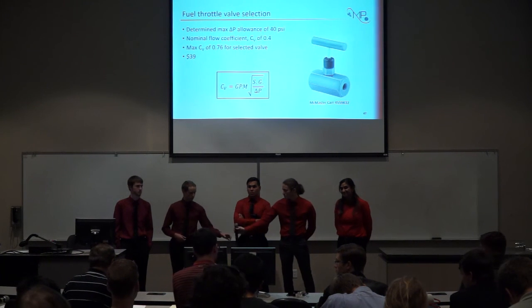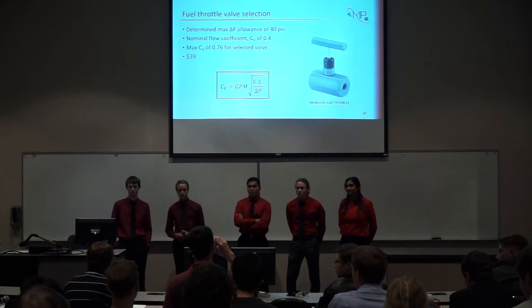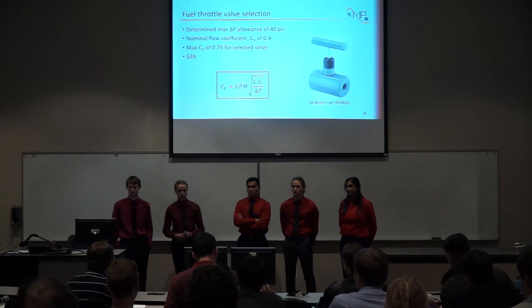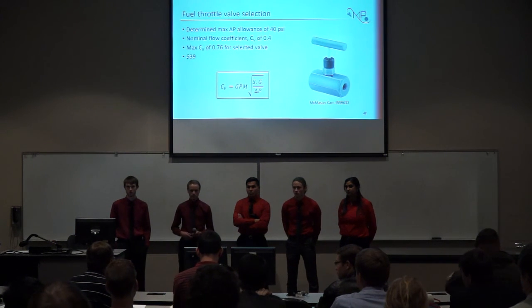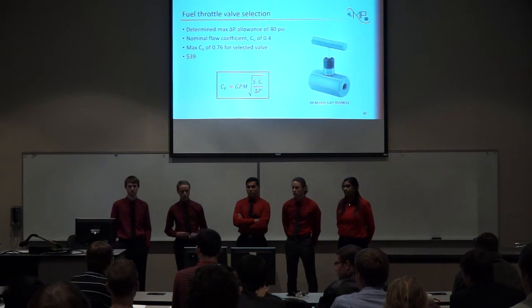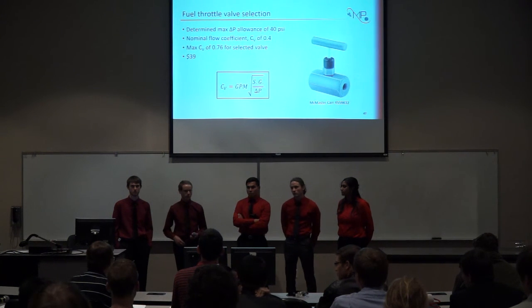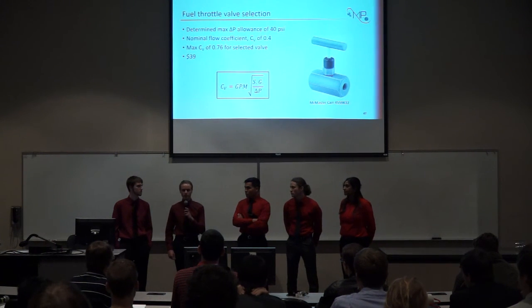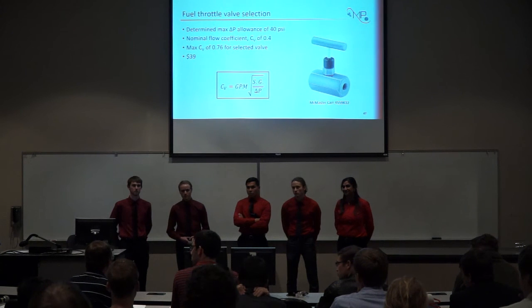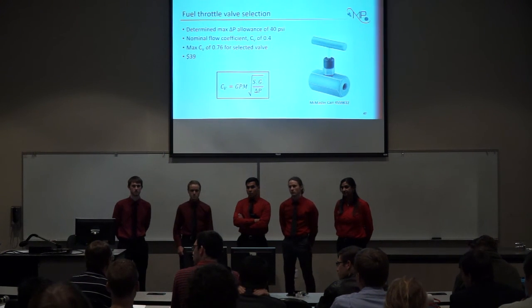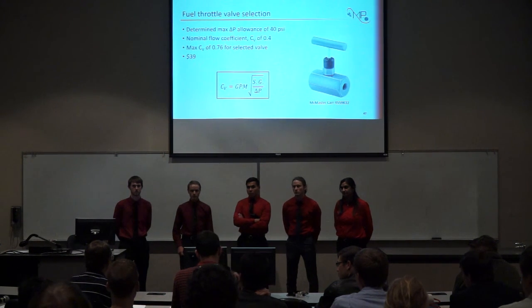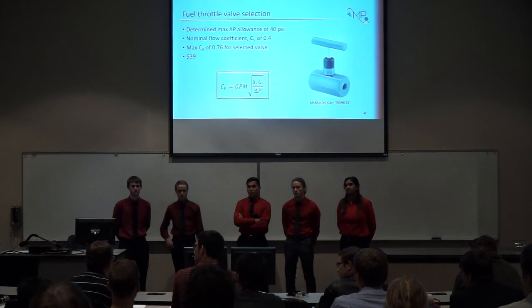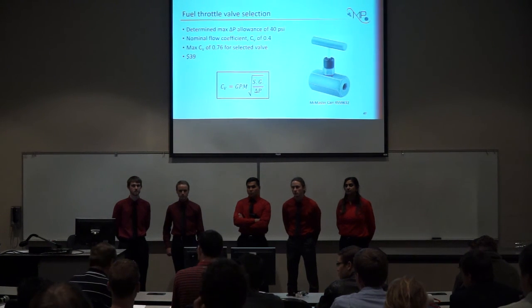Okay, nice job. Are you measuring T in and T out of the cooling water? I saw on the GUI at least one that was labeled, but I didn't see the other. Are you planning to track that? Yeah, we are planning on tracking those temperatures. Don't be surprised if you get big time lags on this, especially if you're only running 5 seconds. Check the sensitivity of all your instruments in terms of response rate, because this thing may lag miserably.